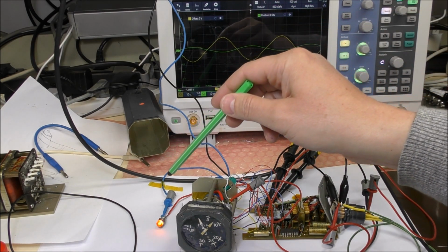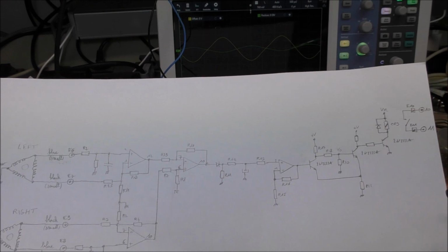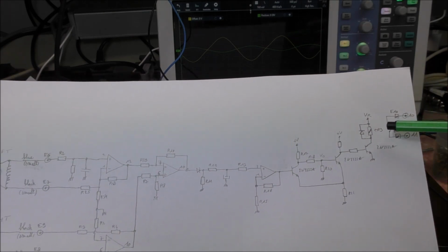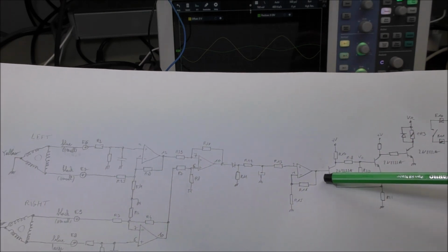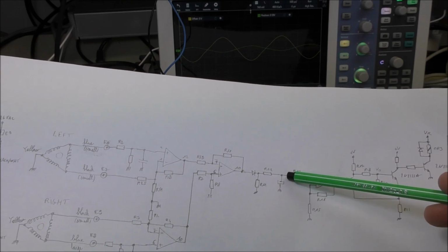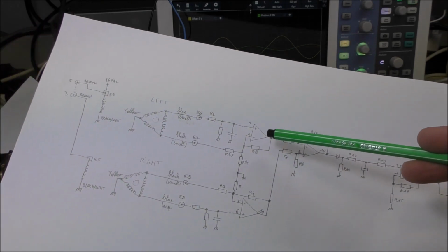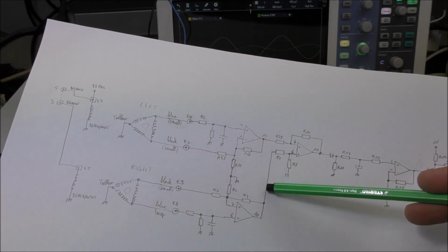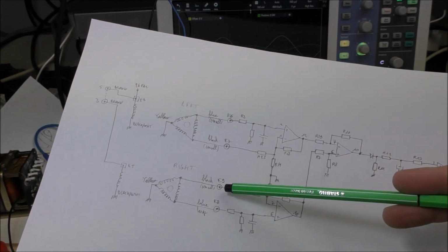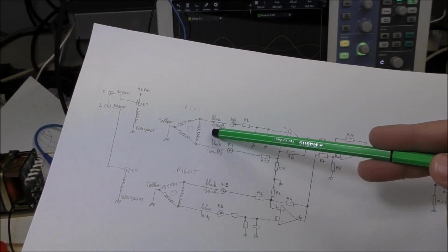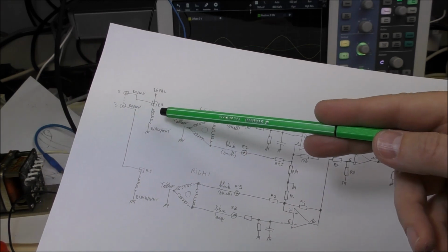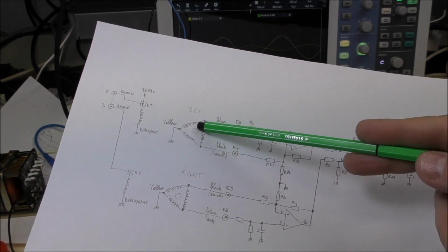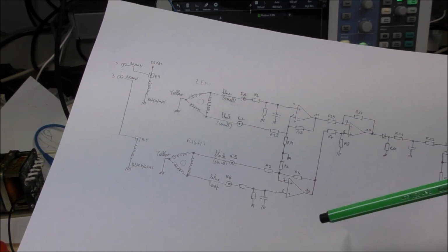So this indicator indicates also the state of the relay. So just to remind you, this relay is here. The relay is activated when the signal here is above a given limit, and the signal is the difference of the two AC signals which come from the two synchros here. And the sensor actually is connected in parallel to the synchro. It's a resolver. It's connected in parallel to the rotor here and to the coils of the stator here. And the second is left open.